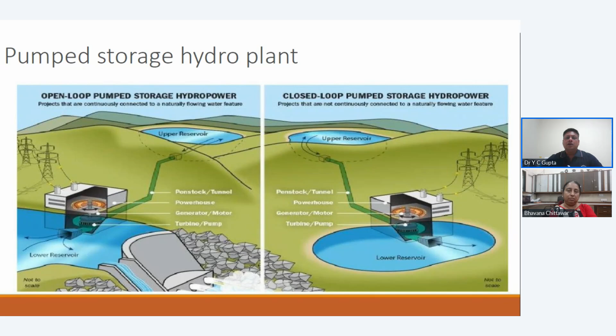These are some characteristics of why pumped hydro storage is so popular. Projects may be practically sized up to 4,500 megawatts. Round trip efficiency is around 76 to 85%. Long life cycle, on the order of 50 to 60 years - as per my knowledge, there are some pumped hydro storage facilities more than 100 years old in the world. General rule: a reservoir 1 kilometer in diameter, 25 meters deep, with an average height of 200 meters, would hold enough water to generate 10,000 megawatt hours.